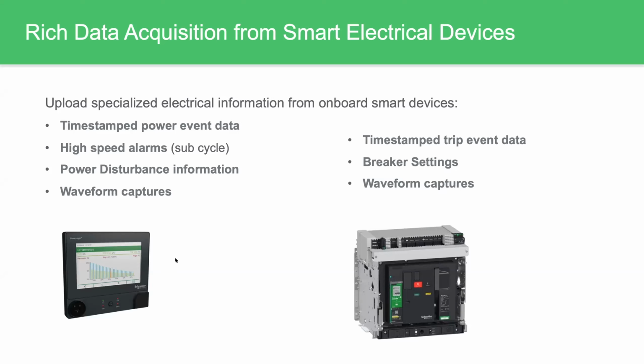Similarly, but typically not as complex, are intelligent circuit breakers. These devices have timestamped trip event data and give visibility to the breaker settings themselves. Also, in some of the higher-end intelligent circuit breakers, there's the capability for waveform capture as well. The breakers are able to capture diagnostic information for each event they see.